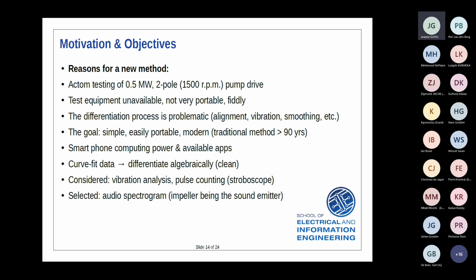I also looked at some kind of pulse counting technique, some kind of stroboscope where you could record a point going round and round. But a common problem with all these techniques is determining when the shaft stops and changes direction. If I'm taking a pulse and it's slowing down and it stops, I don't know where the next pulse goes, because it could start rotating in the other direction and then the pulse goes. So I don't know where the changeover in direction is. And as I alluded to earlier, it's critical to know when the machine stops so that you can scale it correctly by the lock rotor torque. So that option was ruled out. So we went for the audio spectrogram, and we'll talk about that in a moment.